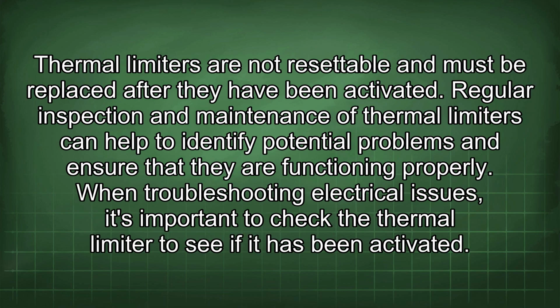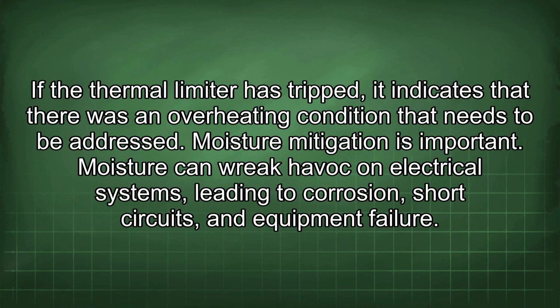Thermal limiters are not resettable and must be replaced after they have been activated. Regular inspection and maintenance of thermal limiters can help to identify potential problems and ensure that they are functioning properly. When troubleshooting electrical issues, it's important to check the thermal limiter to see if it has been activated. If the thermal limiter has tripped, it indicates that there was an overheating condition that needs to be addressed.